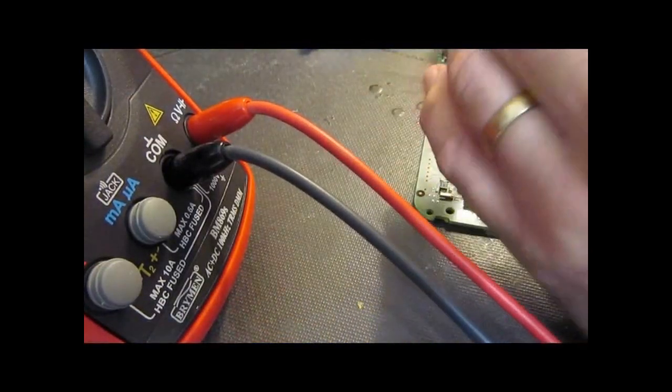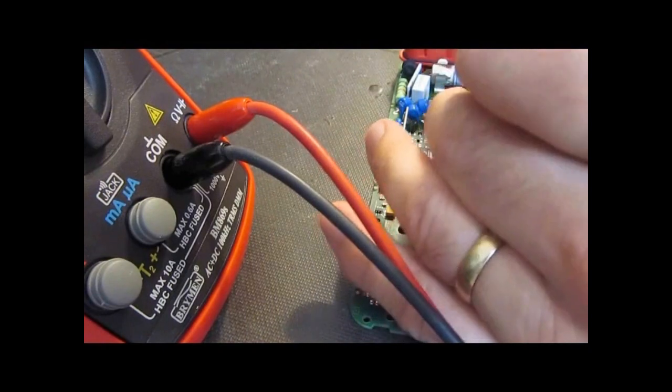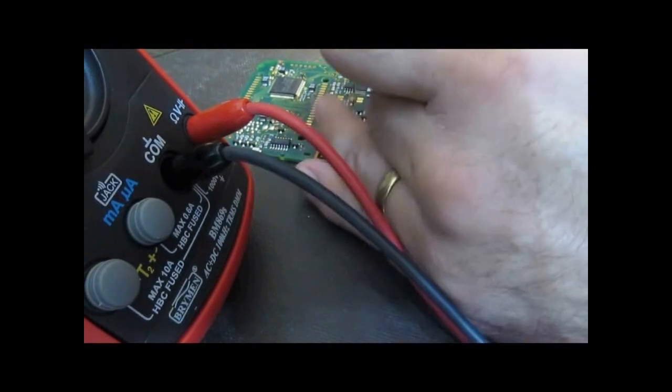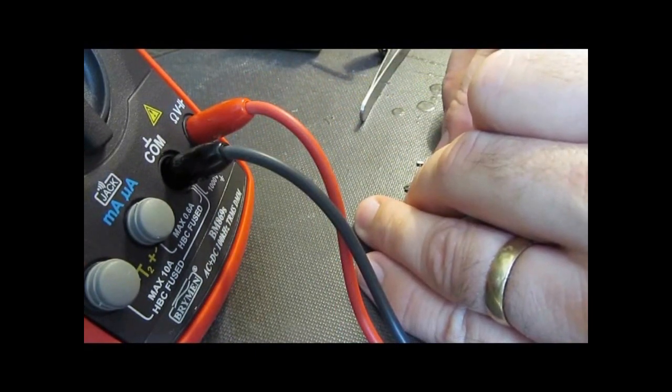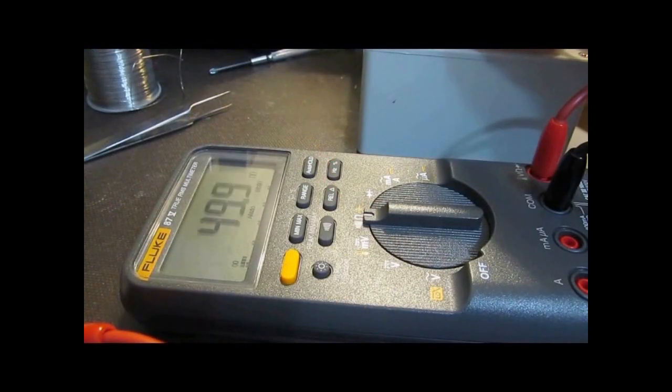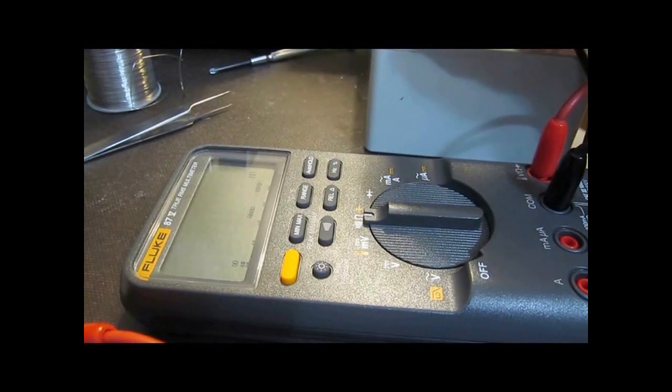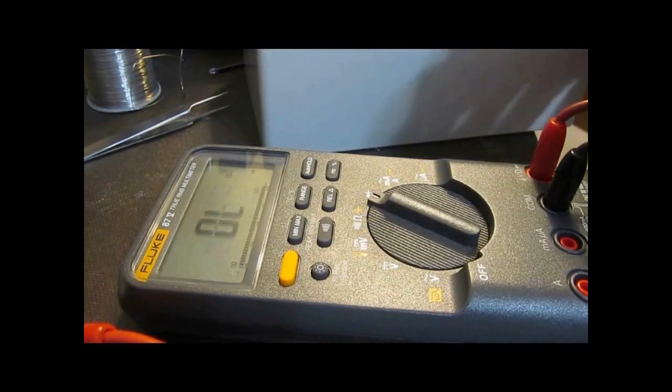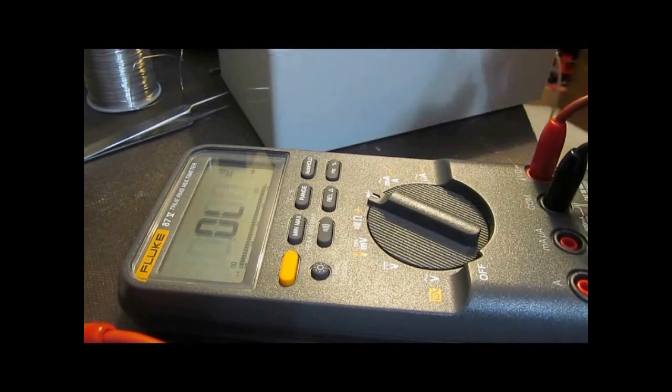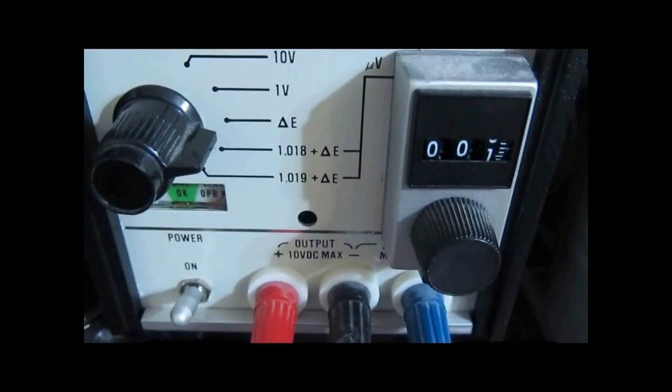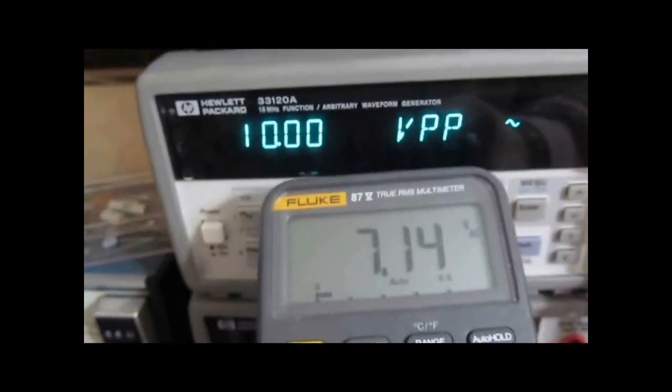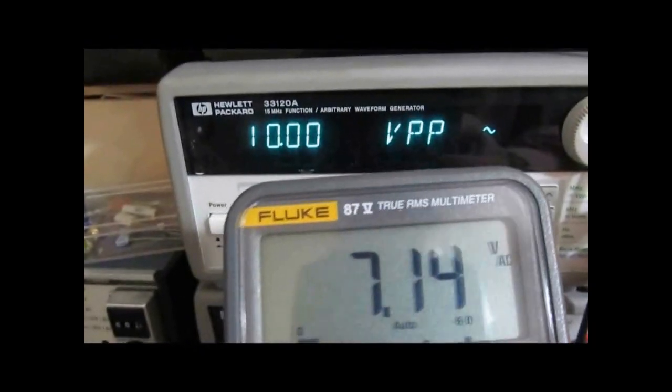We'll use the Brymen here to try to troubleshoot the 87V. Hopefully it's just a diode. Testing 50 ohm, 100 ohm, 100 nanofarad, diode check - looks good. Here we're supplying one millivolt. I didn't think it would ever fail at 1.5 kV, but that seems to be the case. Unreal.